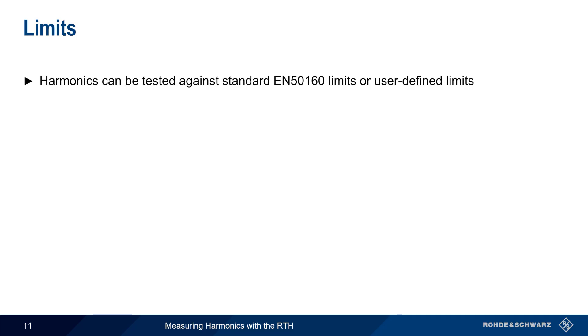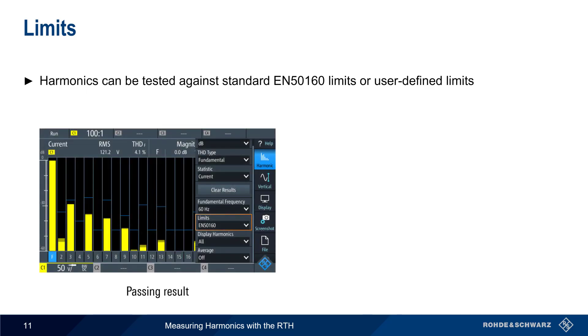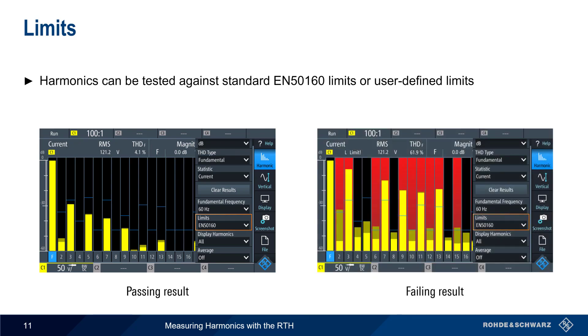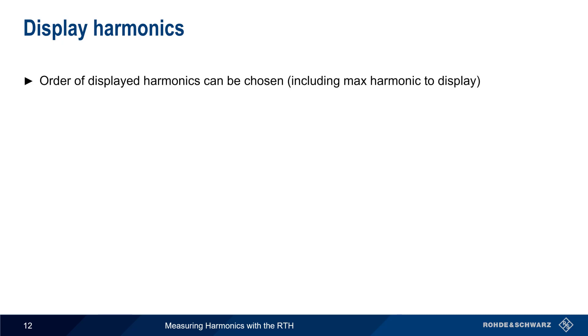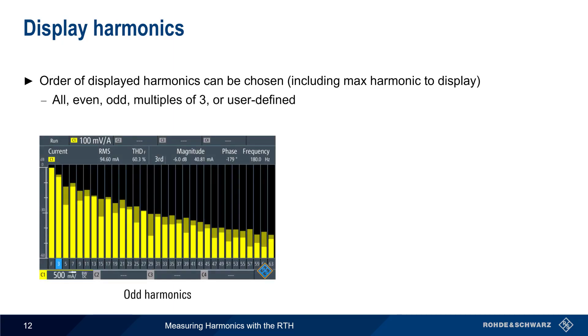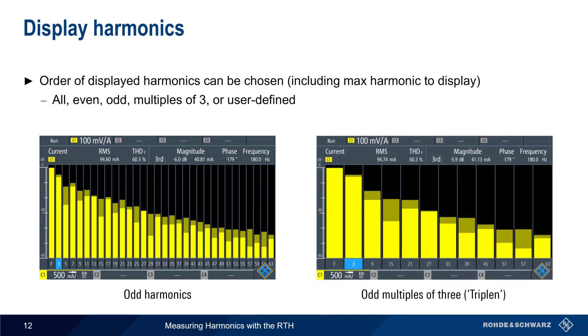One of the most common harmonic measurements is testing against limits, either the standard EN50160 limits or user-defined limits. The per-harmonic limits are shown as blue horizontal lines. For example, this device under test easily passed the EN50160 limit test, whereas this one does not. Violations are shown in red, and an 'L' error indication is displayed as well. The RTH can also be configured to display only certain harmonics or only harmonics up to a certain order — for example, only the odd-order harmonics, or only triplen harmonics, that is, odd harmonics whose orders are multiples of three.